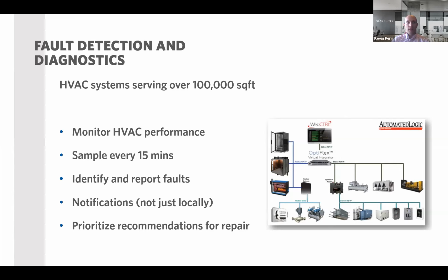And I will say that the last thing that it has to be capable of doing is prioritizing recommendations for that fault. So not only does it have to notify and report, identify the fault, but it also has to identify based on the data collected from the HVAC system, that every 15-minute interval, it has to prioritize and come up with recommendations for repair on that fault. So that's quite a bit there. Not too many building automation systems do that automatically.